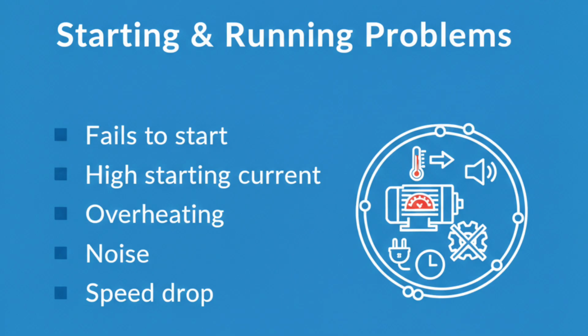Operational problems such as the motor failing to start, drawing excessive current at starting, overheating in running condition, abnormal humming noise, or drop in speed usually indicate either electrical supply issues or mechanical overload. For example, failure to start may be due to low voltage, faulty contactor, or jammed load, while overheating may be caused by blocked ventilation or overloaded pump.